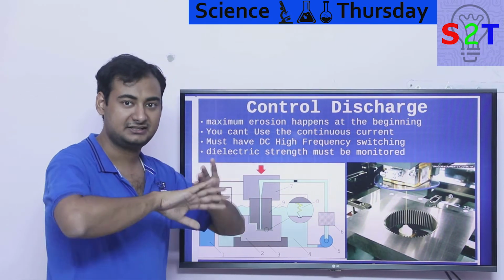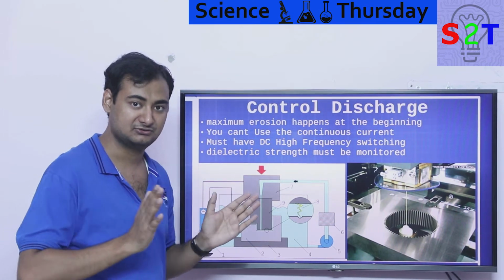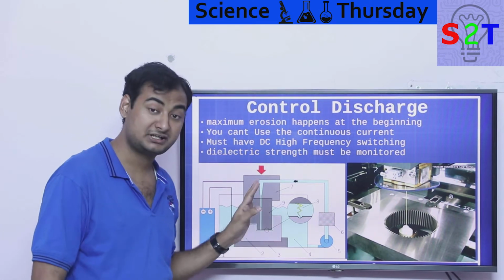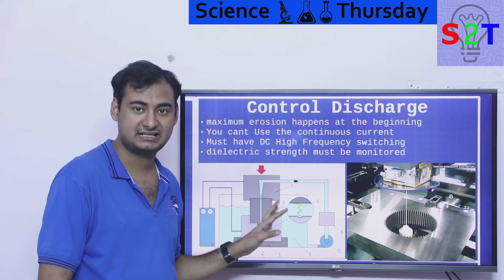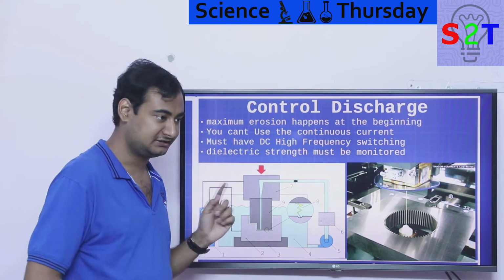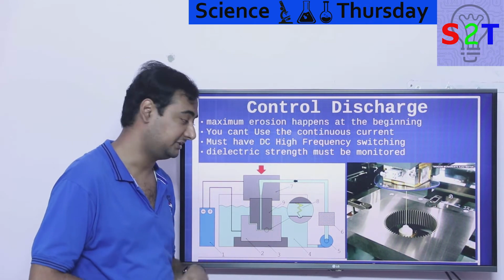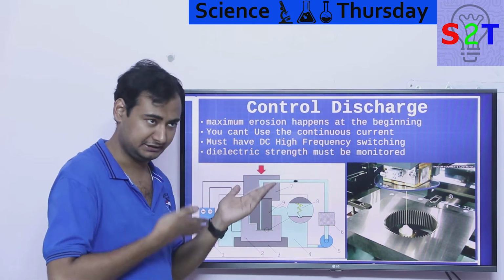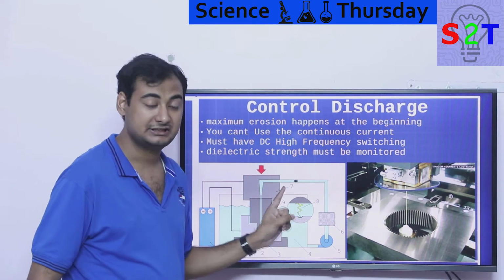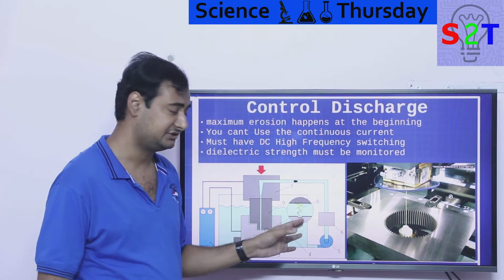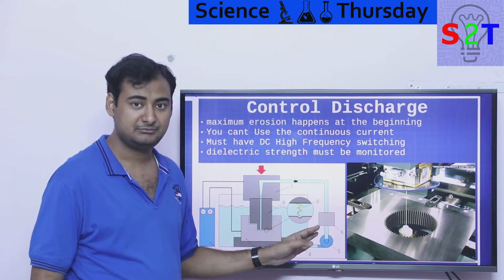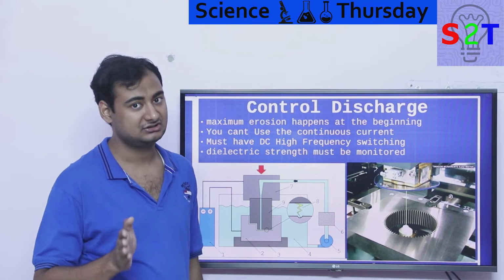So water is acting as a removable thing, it's removing everything. And water must be maintained -- you cannot just have the water, you must understand its temperature and electrical conductivity, and you must send it through a pump again. So you can pump everything, and there are also generally ion membrane exchange filters and all that, so we can maintain the conductivity to a certain level.